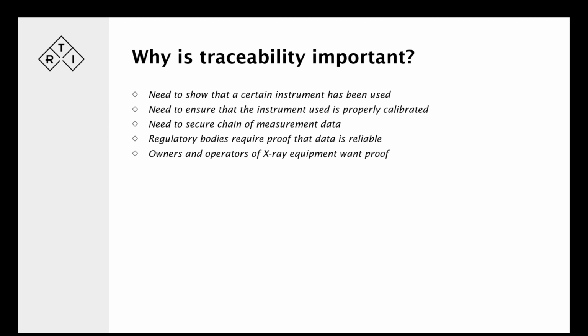So owners and operators of X-ray equipment, so that's hospitals, and that could be clinics, it could be others that lease equipment or that kind of thing, that need to know that the equipment they have, what shape is it in? And to determine that, a part of that is tested with the equipment that we provide when doing preventive maintenance tests or yearly tests that are not for a regulatory body, but other tests to ensure that the system is functioning properly.